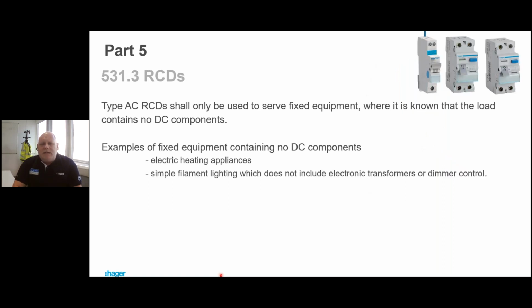Okay, RCDs. These RCDs turned RCD selection on its head a couple of years ago. So type AC RCDs are not used very often now, but you will come across installations where they are still installed. So it says type AC RCDs shall only be used to serve fixed equipment where it is known that the load contains no DC components.